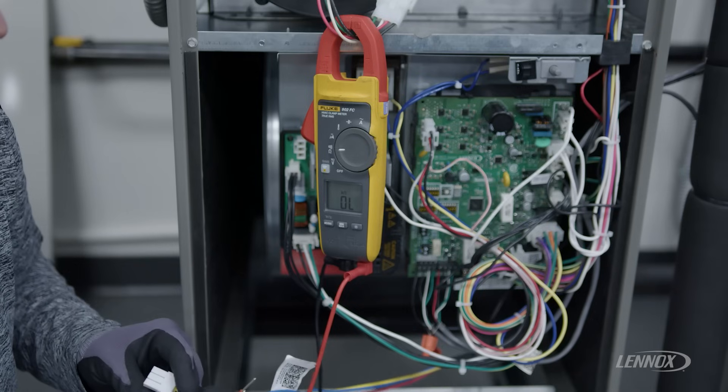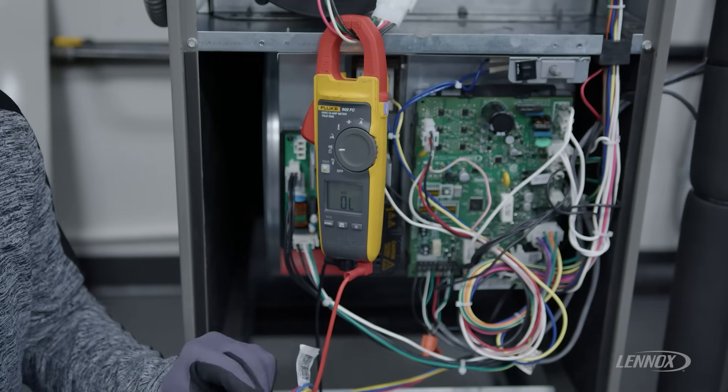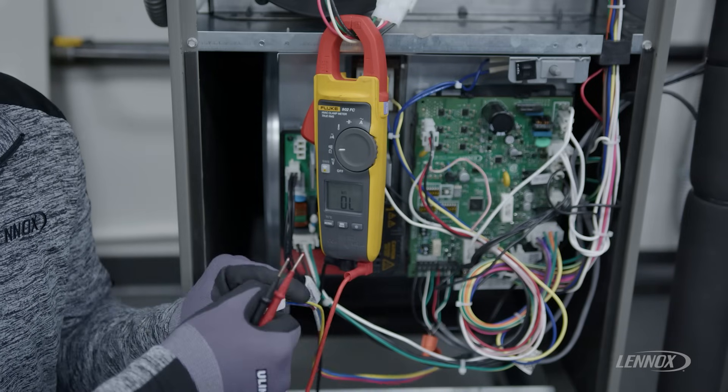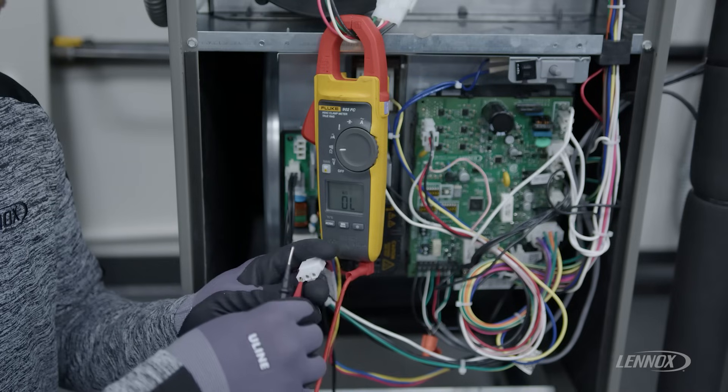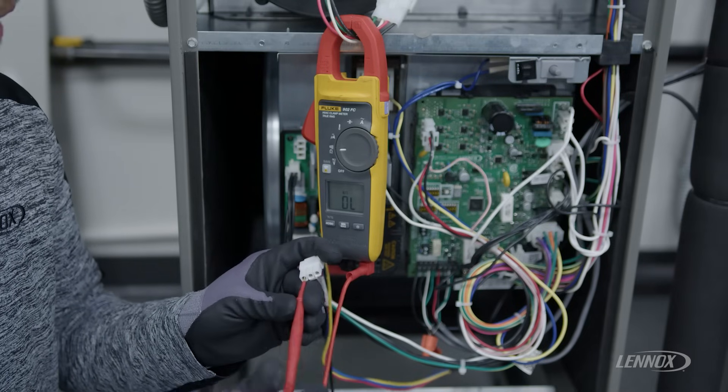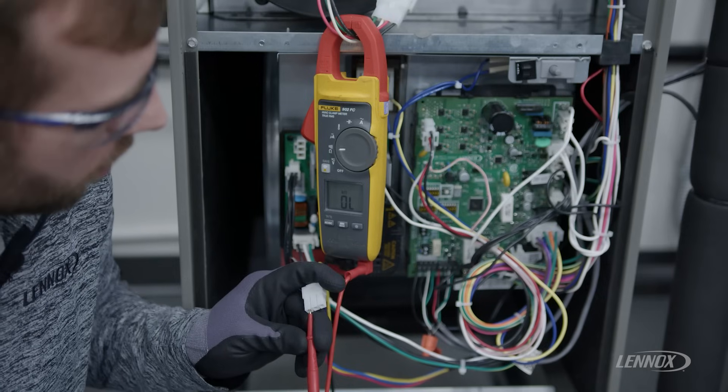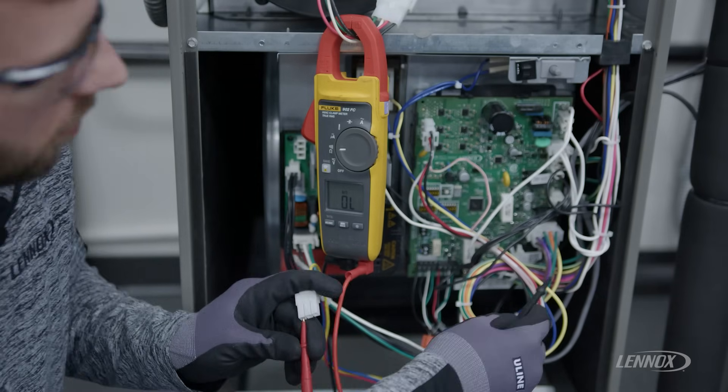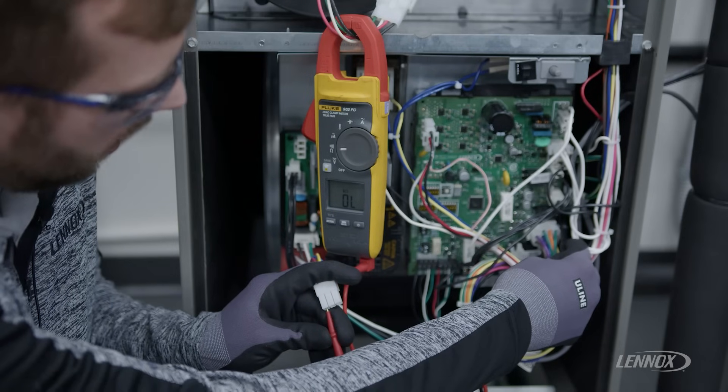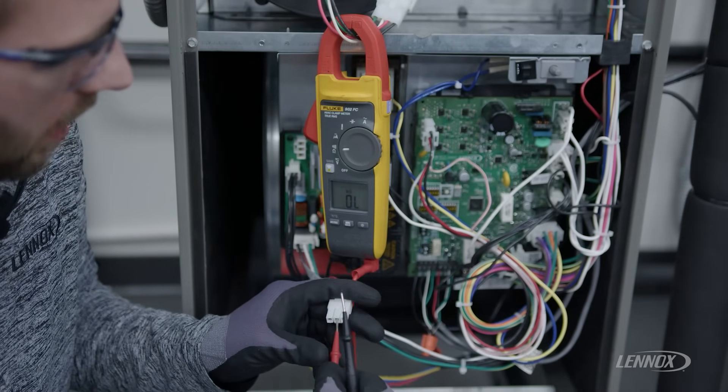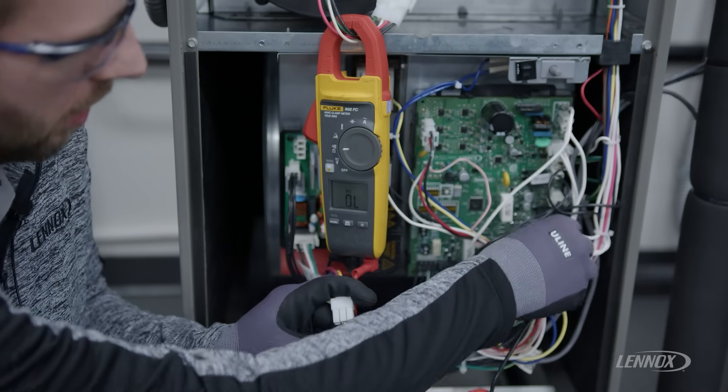The last test that you would want to do to verify the integrity of the motor is to check the resistance of each of the windings to earth ground. To do so, you would simply take one lead from your meter into one slot of your molex plug, and take your other lead and test it to a good earth ground. A good reading on each of these should read infinite ohms, indicating that we have no continuity between any of the motor windings and ground.